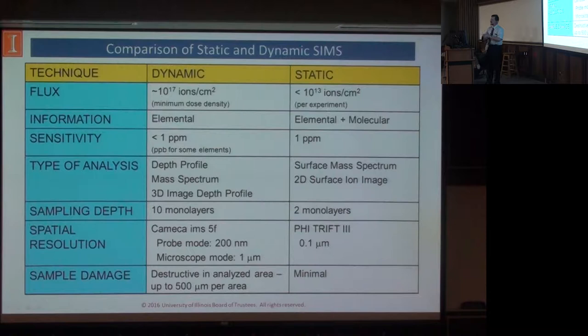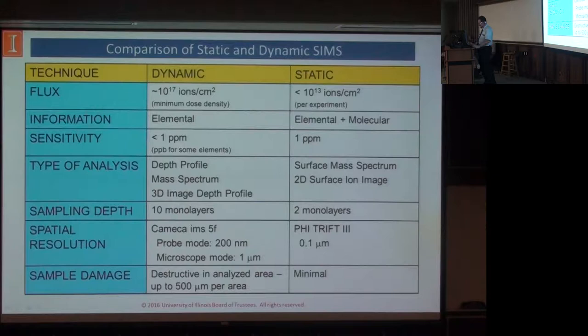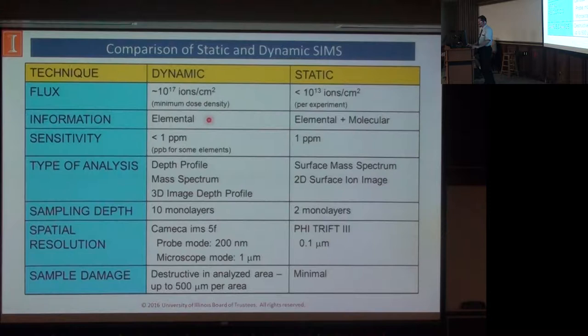In SIMS we tend to talk about two regimes: static SIMS and dynamic SIMS. Dynamic SIMS is the older of the two — you're constantly churning away and removing material. If someone asks whether SIMS is non-destructive, you can ask them how big of an area needs to be non-destructive, because we are going to make a crater, especially if you're doing dynamic work. A downside when doing all this sputtering is you tend to mix everything together, so when you're doing depth profiling you're really limited to elemental work, although there are now situations where they're getting past that. Dynamic SIMS offers very high sensitivity — parts per million type things.